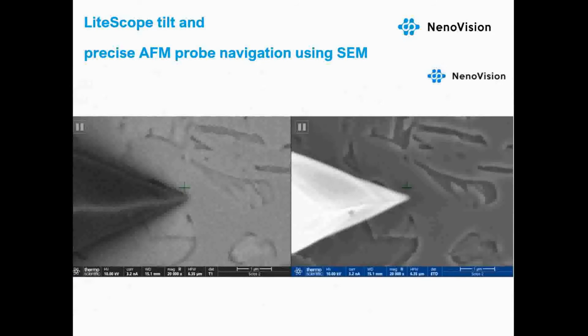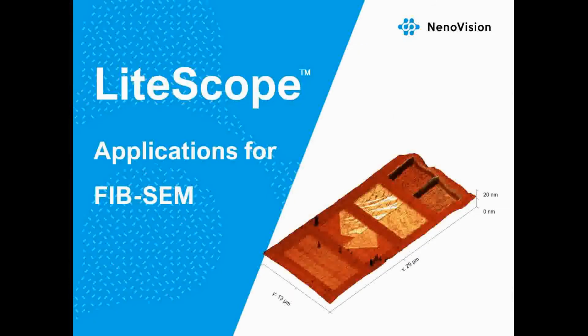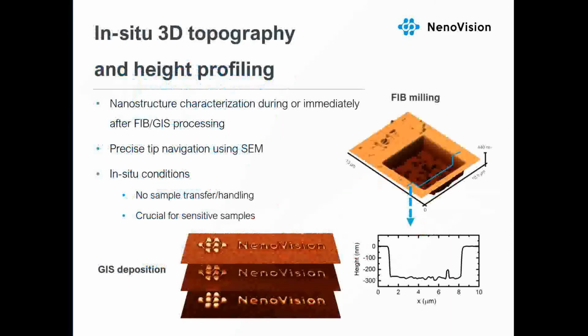Now let's talk about the main application areas for combined AFM and focused ion beam SEM instruments. Let's start with the most straightforward feature of integrating AFM within SEM equipped with focused ion beam, which is in-situ topography and height profiling of FIB and GIS structures. Depending on the application, the AFM topography analysis can be performed during or right after the FIB processing.